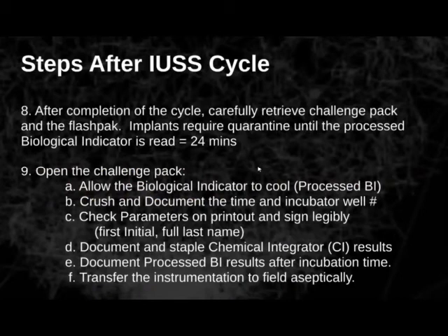The implants require quarantine until the processed biological indicator is read in 24 minutes. So that quarantine is your scrub person isolating it to the side until the results are read. Open the challenge pack. Again, be cautious because it would be hot. Allow the biological to cool.